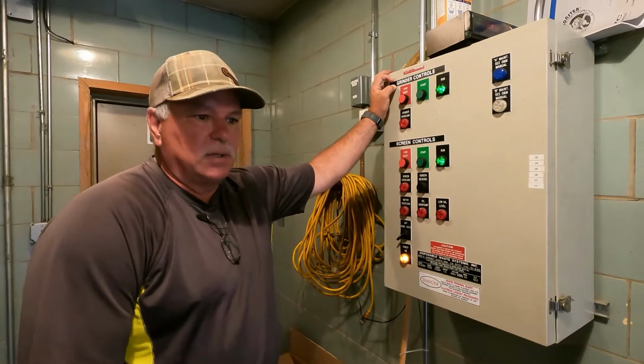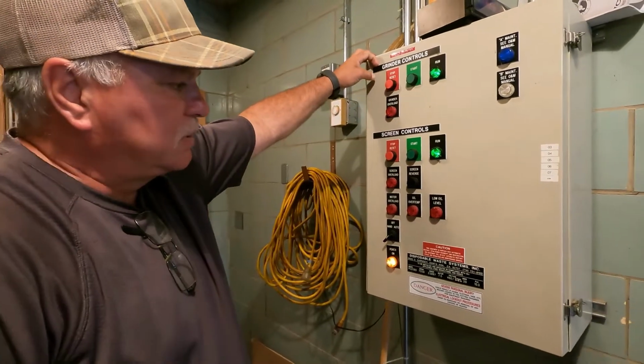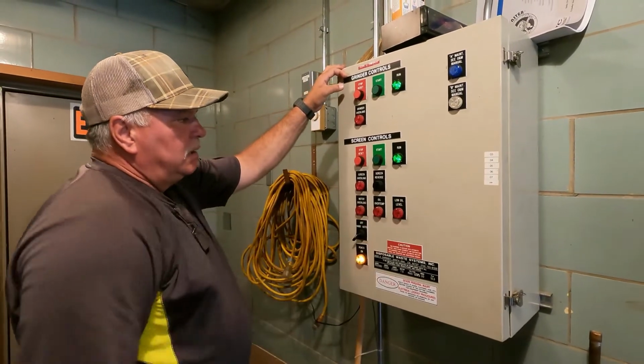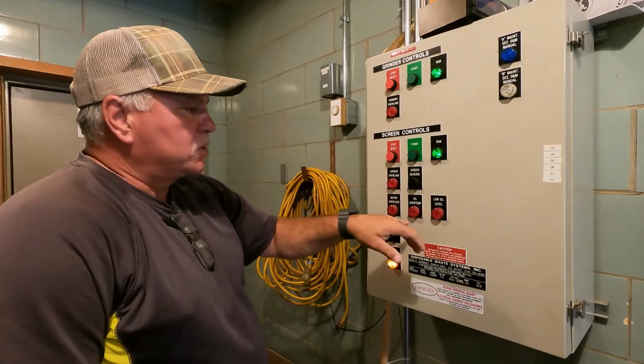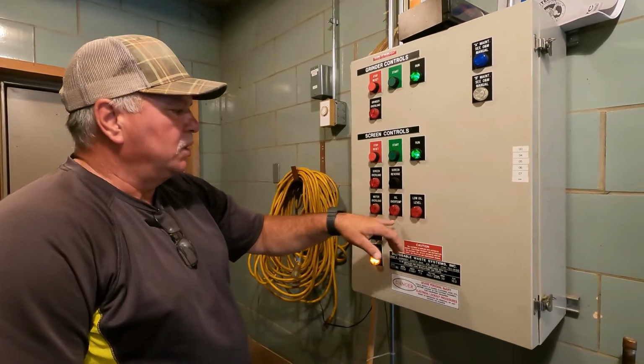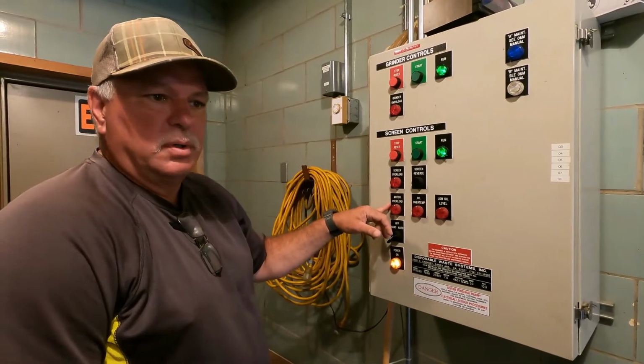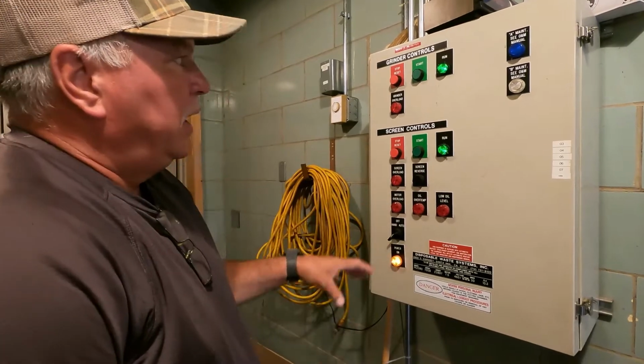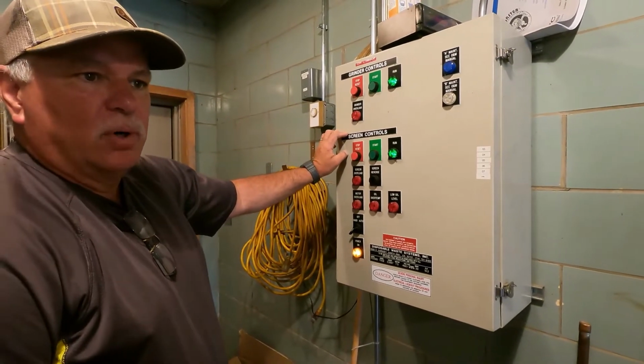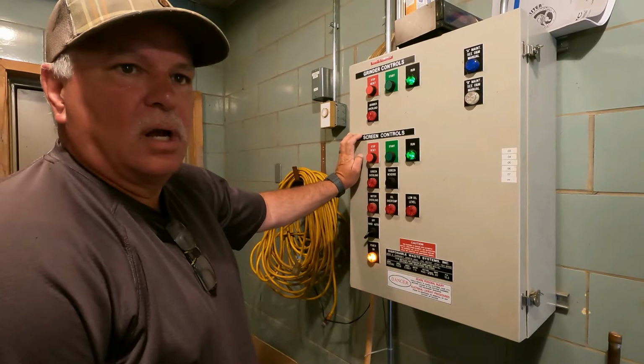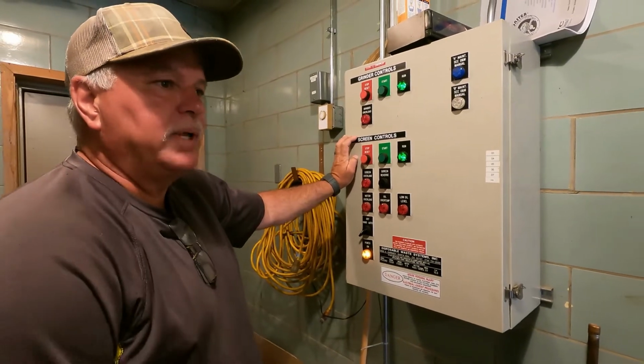Control for the Muffin Monster that's in the wet well. This would technically let you know if you are low on oil pressure, temperature, or motor overload due to the grinder being jammed. And this is actually where the alarm would sound if there was a jam in the grinder itself.